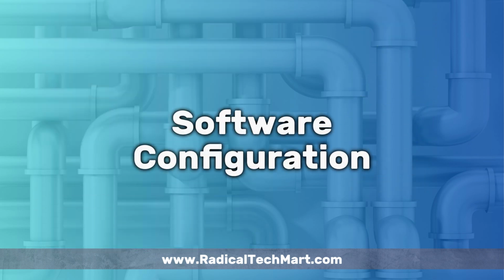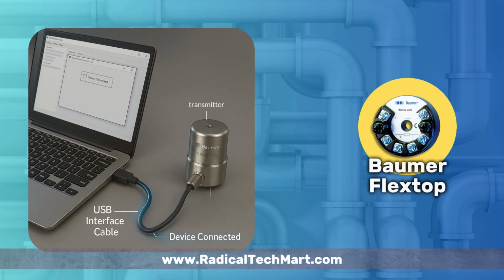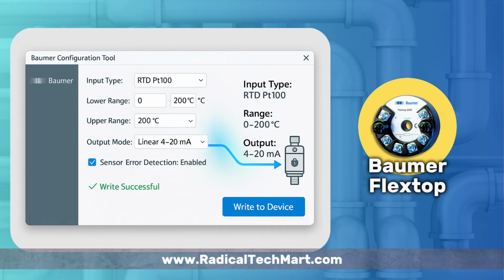Now let's configure the transmitter using the Baumer configuration tool. Connect the USB interface cable from your laptop to the transmitter. Once it's detected, open the software and select the correct input type, RTD PT100. Set your desired measurement range, for example 0 degrees Celsius to 200 degrees Celsius, and choose linear output 4 to 20 mA. Click Write to save the parameters. You can also enable sensor error detection. This helps identify broken RTD wires in the field.